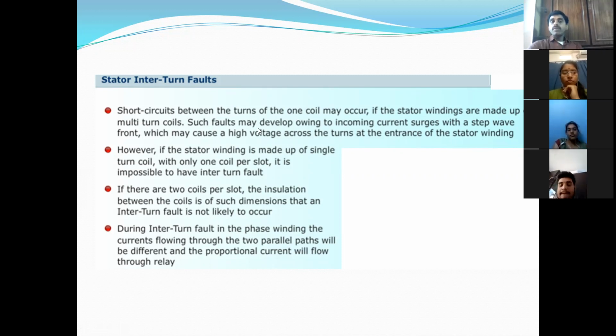How to protect? However, if the stator winding is made up of single turn coil, it doesn't result in any interturn fault. That means with only one coil per slot, it is impossible to have interturn faults. If there are two coils per slot, that means in one slot there are two coils, double layer. The insulation between the coils is of such dimensions that an interturn fault is not likely to occur, because they have separate provision for that. During interturn fault, in the phase winding, the currents flowing through the two parallel paths will be different, and the proportional current will flow through the relay. We'll discuss this very clearly.